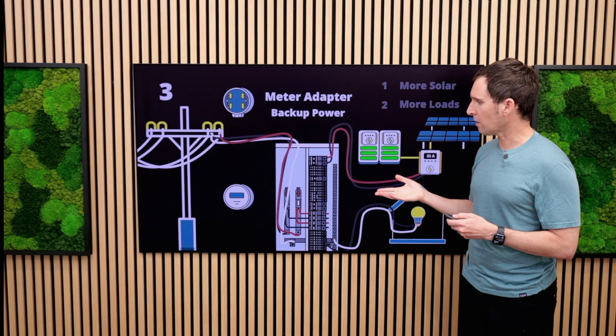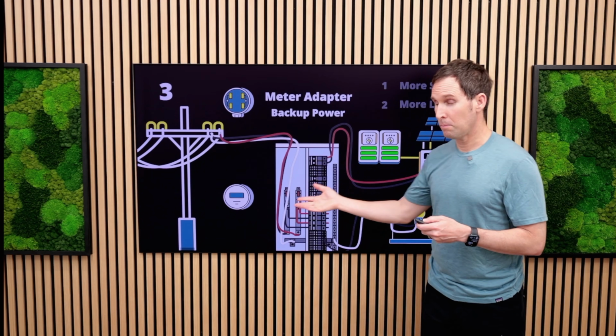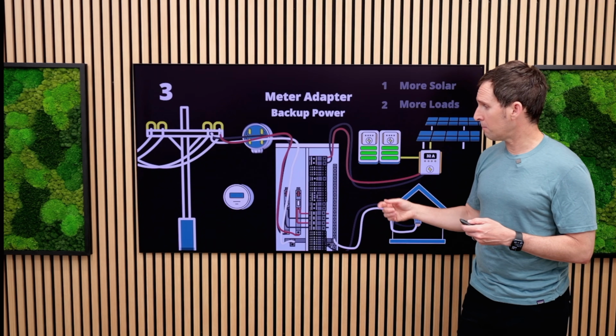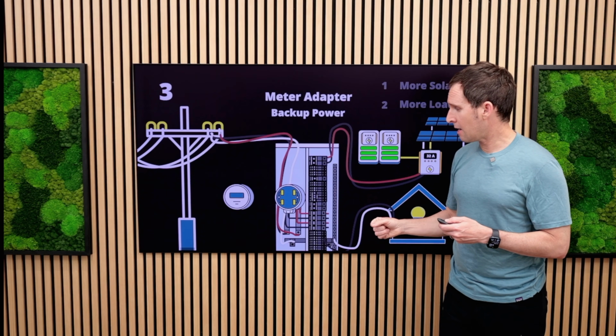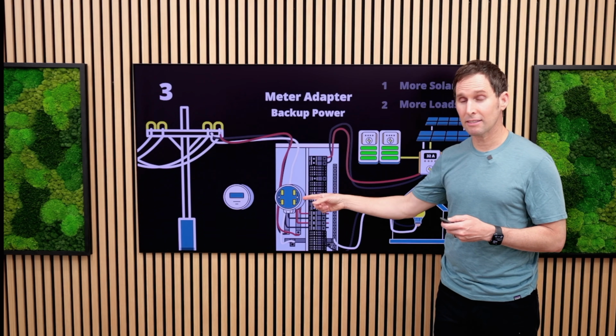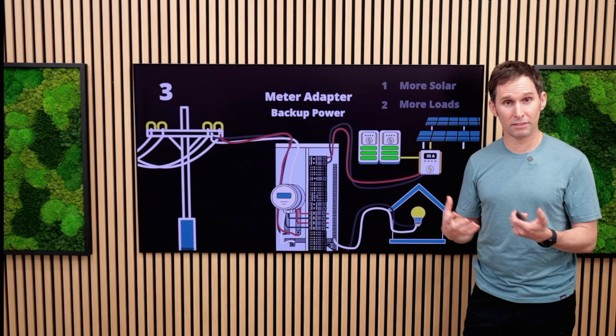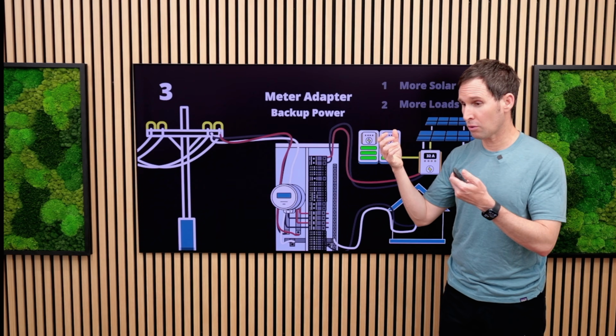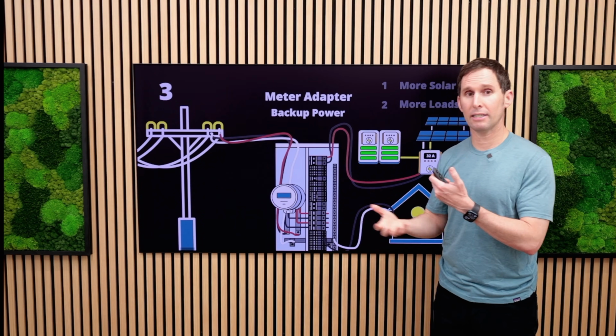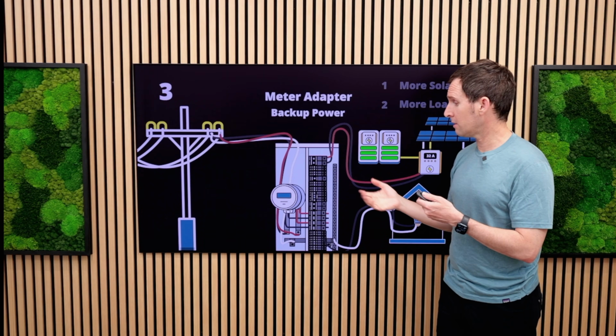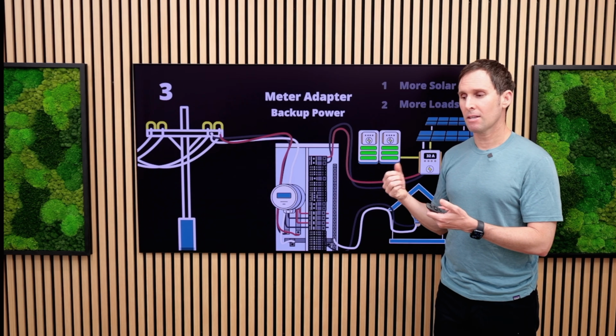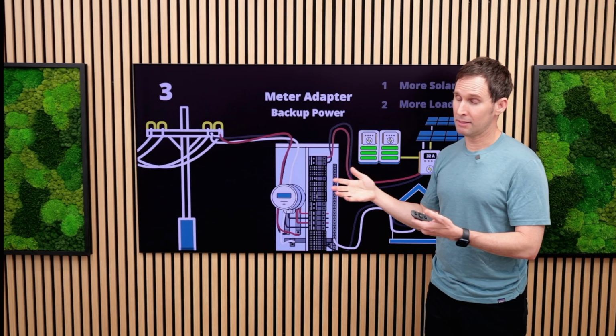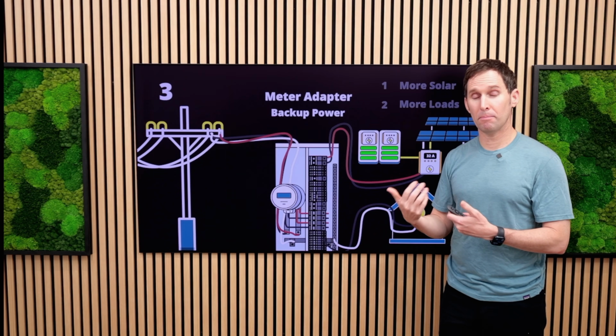The way that works is you pull the meter, install a meter adapter, and that adapter has a disconnect. I mentioned there are different types of adapters: one was a tap for solar, one was a tap for loads like an EV charger or a sub panel. This one would have a special disconnect. Some even have a disconnect and maybe even an input as well.